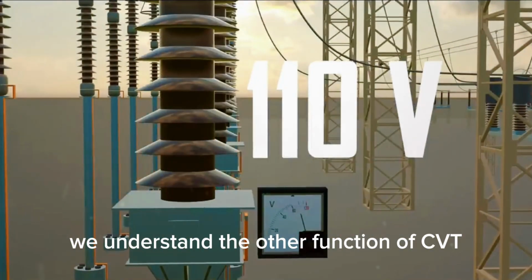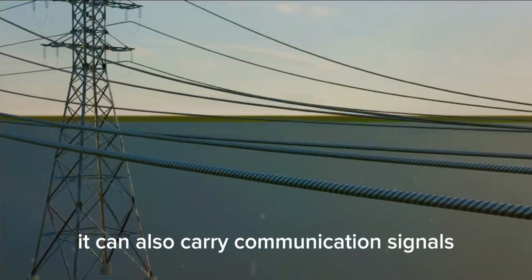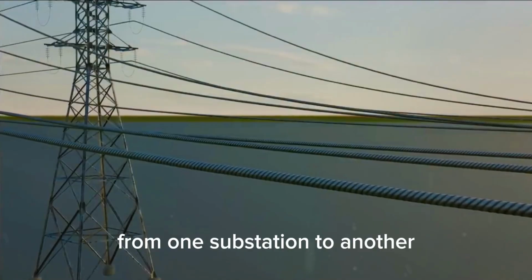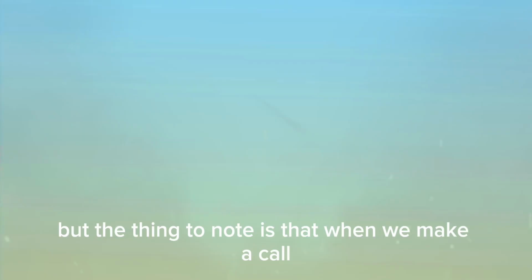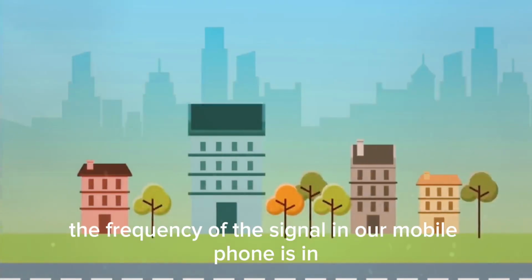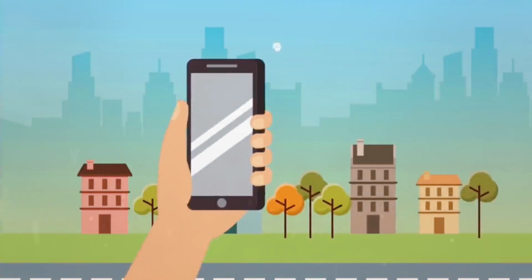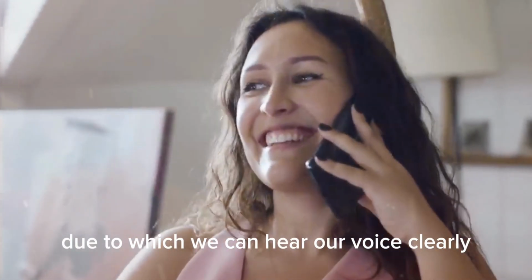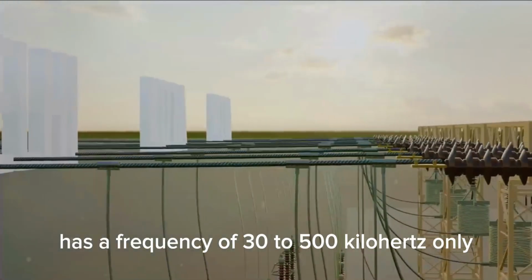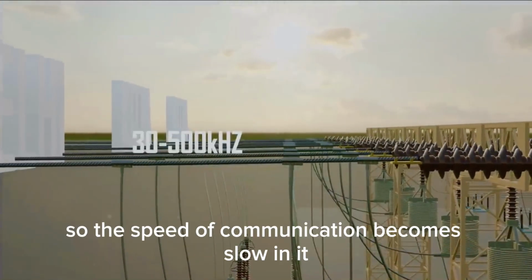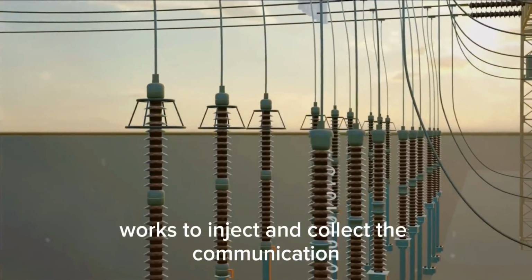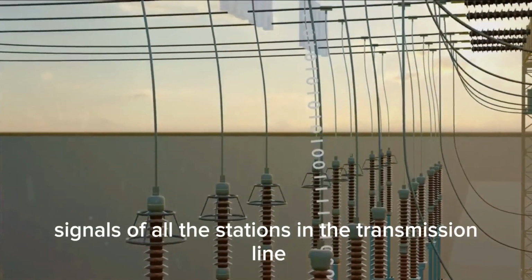We understand the other function of CVT with the help of the wave trap. The transmission line transfers power. Along with this, it can also carry communication signals from one substation to another. But the thing to note is that when we make a call, the frequency of the signal in our mobile phone is in megahertz, due to which we can hear our voice clearly without any delay. But this power transmission line has a frequency of 30 to 500 kHz only, so the speed of communication becomes slow in it.